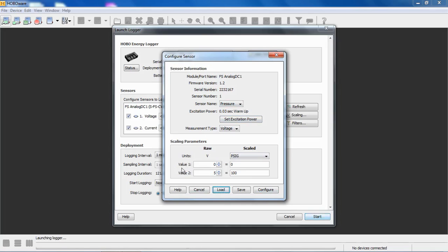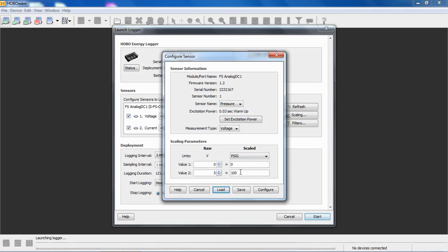And then we can see that at 0% output with 0 voltage out of the sensor, we'll read 0 PSIG, pounds per square inch gauge pressure. And at 100%, we will have a 5 volt output out of that sensor, and that will be represented by 100 PSIG. So your data will be represented as 0 to 100 PSIG instead of 0 to 5. If you didn't scale this, all you would get was that raw 0 to 5 volt output.